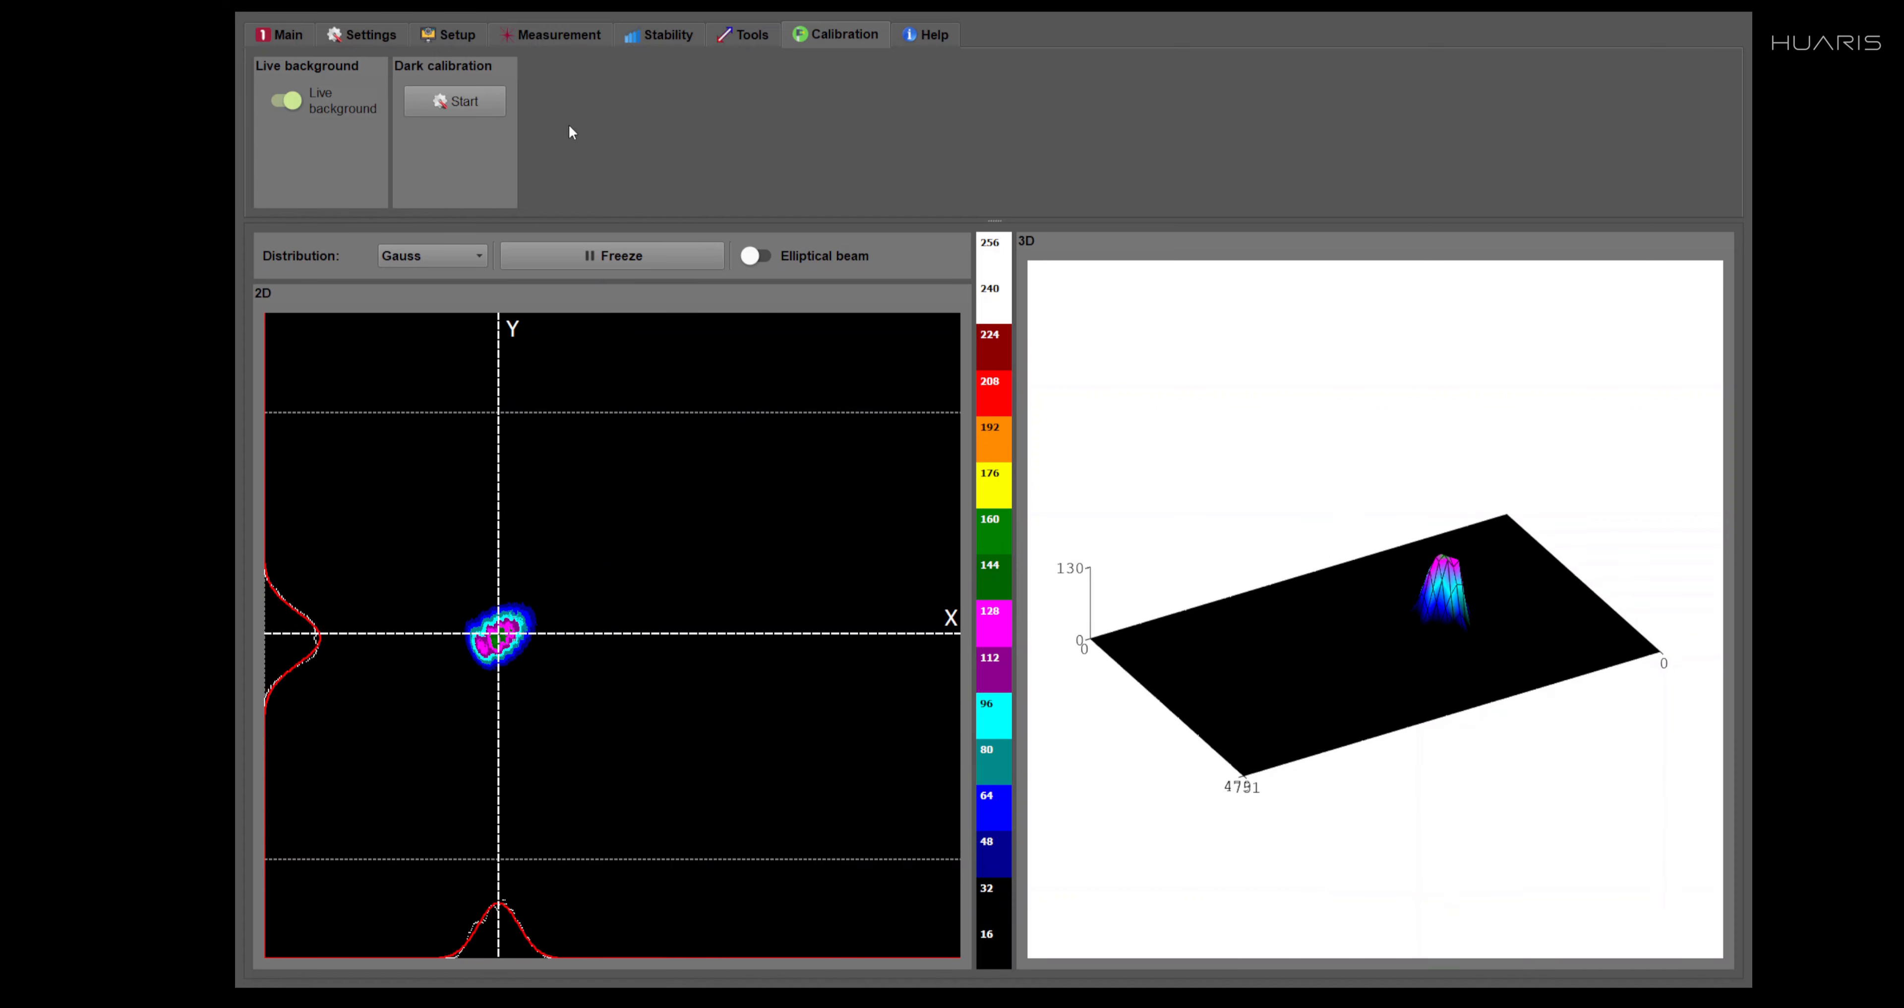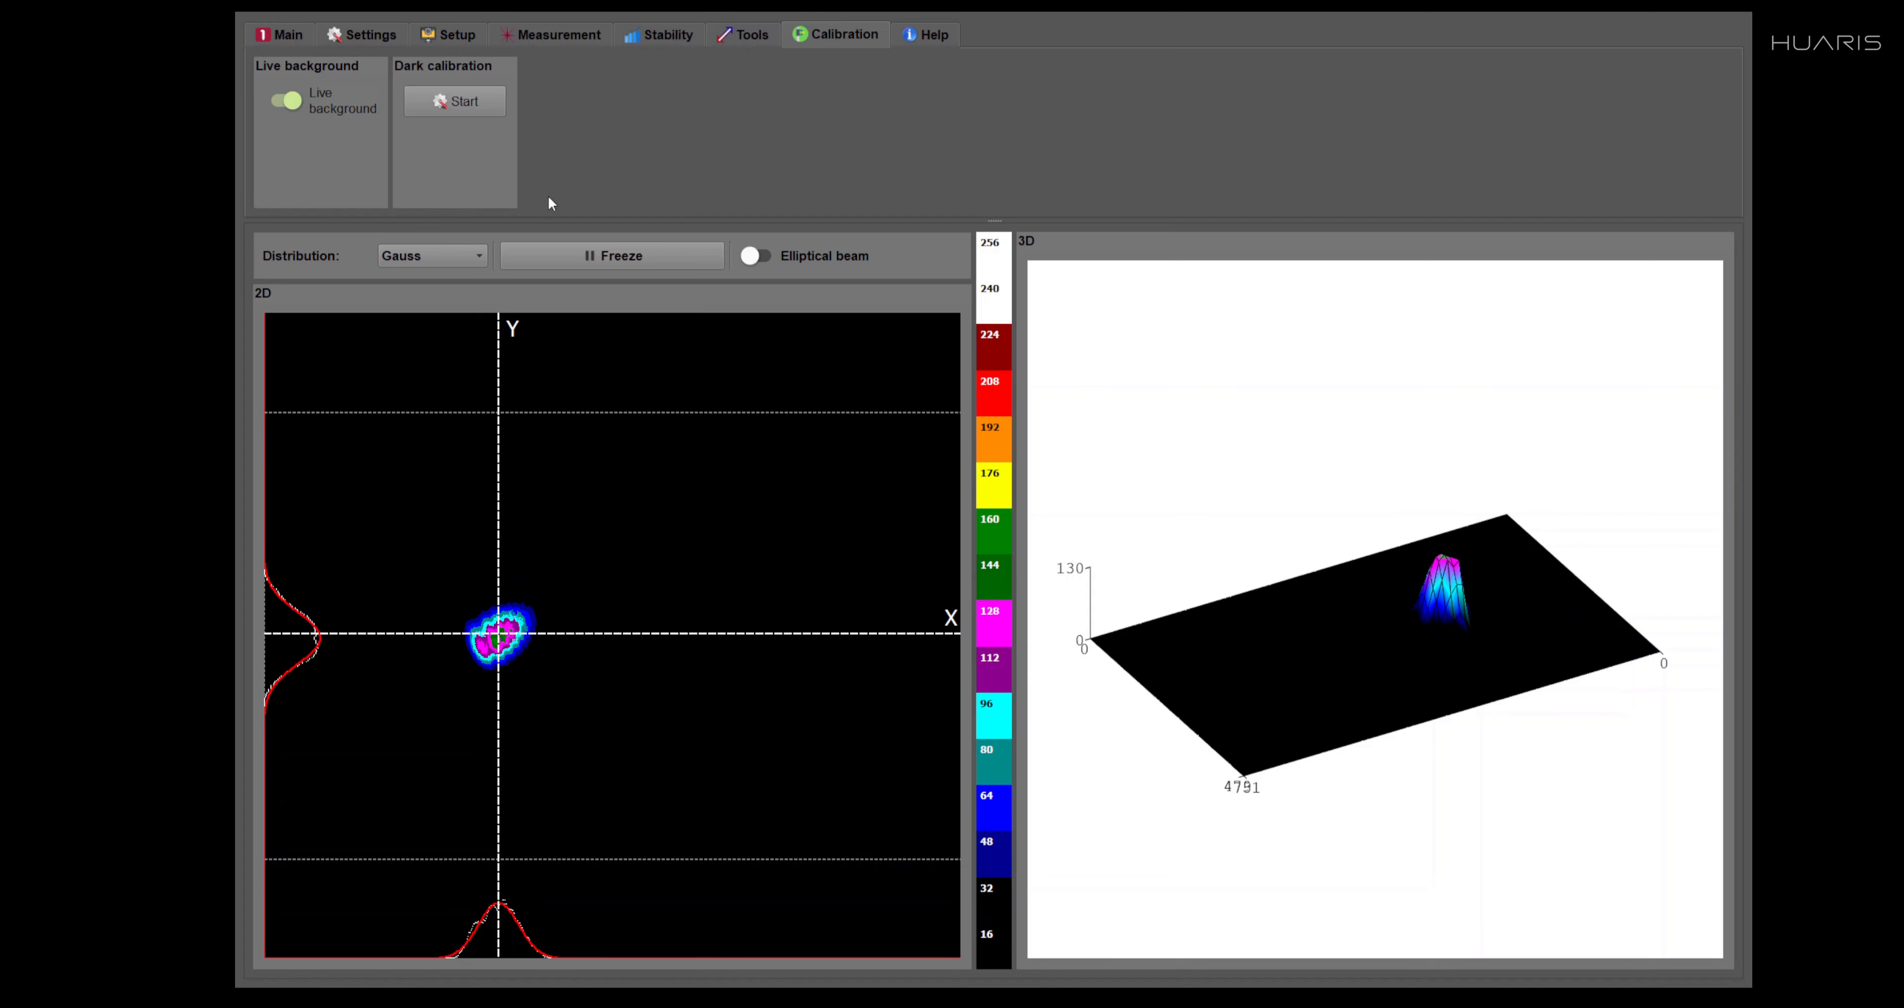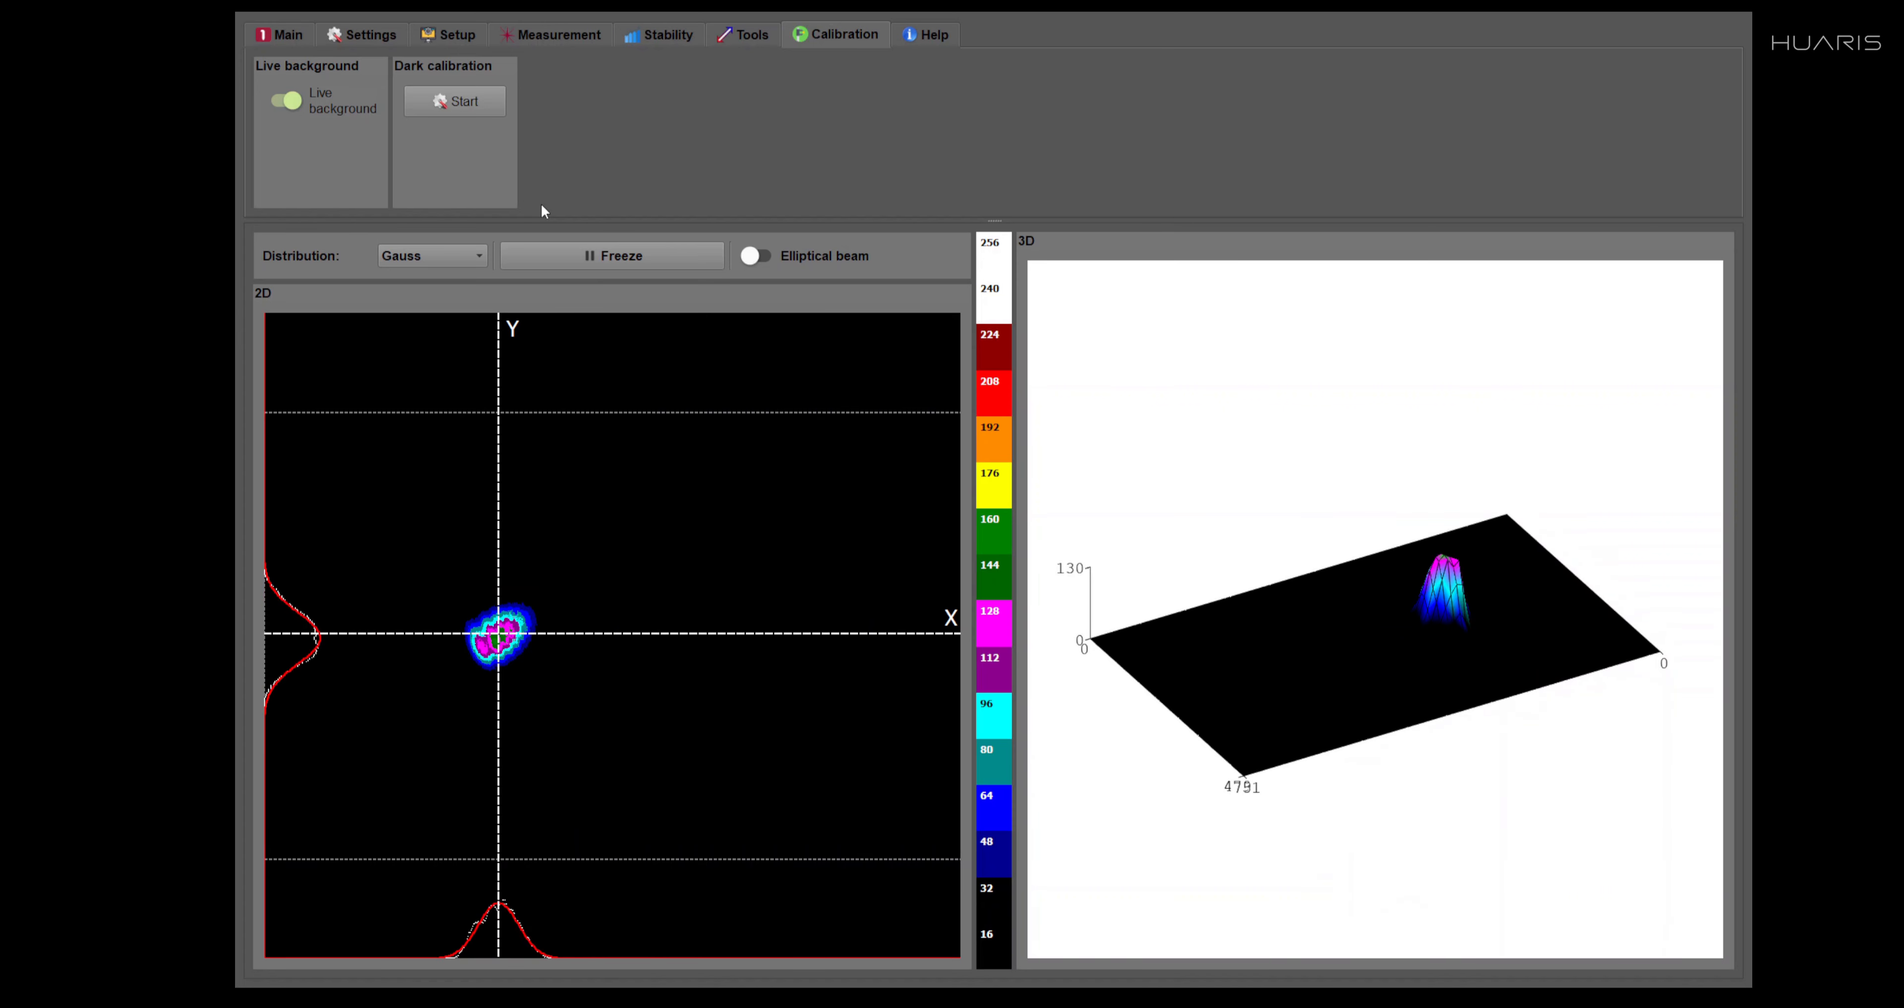What you must know is that this dark calibration is performed with the profiler closed. When we deliver the profiler, you get a cap. Please use that cap to close the profiler before you start dark calibration. This procedure has to be made only once on a given computer when you make the measurement for the first time.